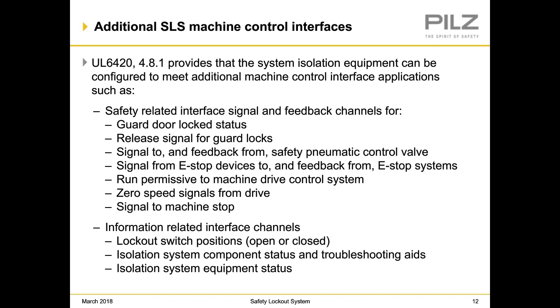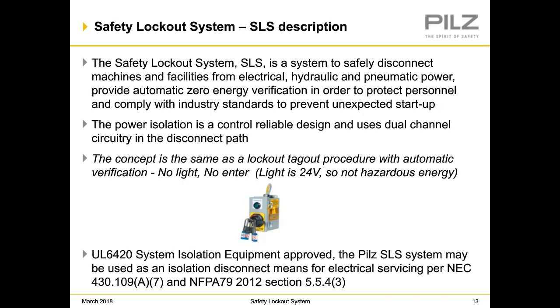So, the Safe Lockout System, what is it? The Safe Lockout System, or SLS, is a system to safely disconnect machines and facilities from electrical, hydraulic, and pneumatic power and provide automatic energy verification in order to protect personnel and comply with industry standards to prevent unexpected startup. The power isolation is a control reliable design and uses dual channel circuitry in the disconnect path. The concept is the same as lockout tagout procedure with an automatic verification. No light, no enter. The light is 24 volts, so that's not hazardous energy.